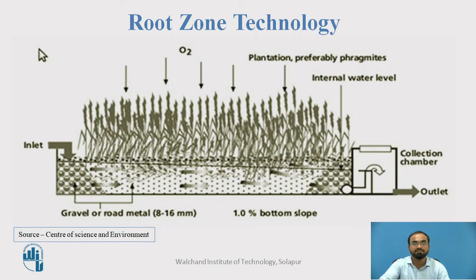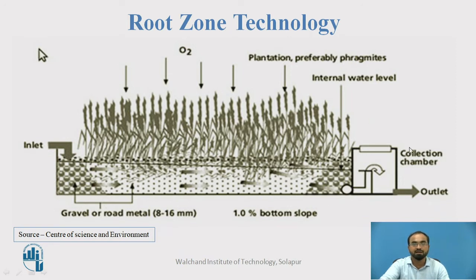In the more detailed diagram, the inlet is shown on the left, and through the gravel the wastewater enters the root zone where the roots release oxygen from the atmosphere. Near the roots, a rhizosphere is created where microorganisms residing on the gravel take in oxygen and organic matter from the flowing wastewater. The gravel should be between 8 to 16 mm in size, and the slope for wastewater flow is around 1 percent. As the wastewater flows slowly, it is treated by microorganisms and taken out from the outlet.